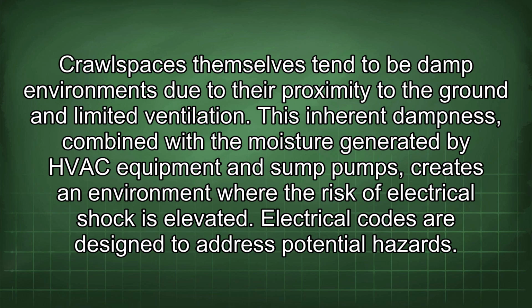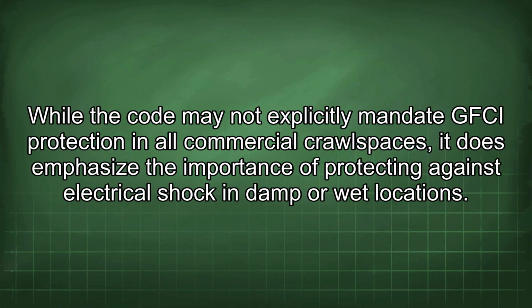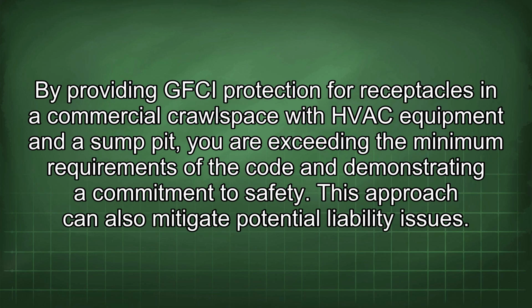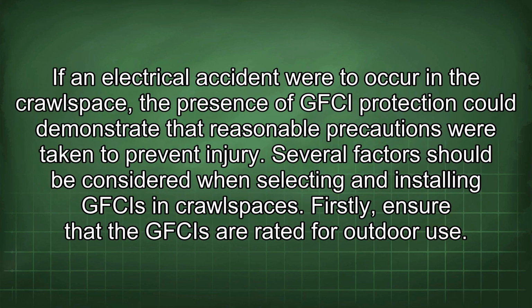Electrical codes are designed to address potential hazards. While the code may not explicitly mandate GFCI protection in all commercial crawlspaces, it does emphasize the importance of protecting against electrical shock in damp or wet locations. By providing GFCI protection for receptacles in a commercial crawlspace with HVAC equipment and the sump pit, you are exceeding the minimum requirements of the code and demonstrating a commitment to safety. This approach can also mitigate potential liability issues. If an electrical accident were to occur in the crawlspace, the presence of GFCI protection could demonstrate that reasonable precautions were taken to prevent injury.